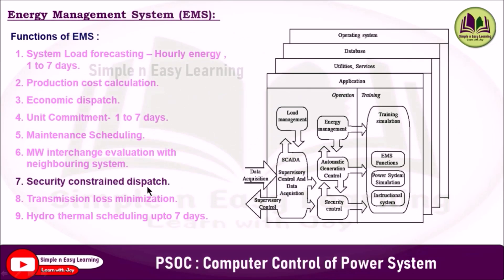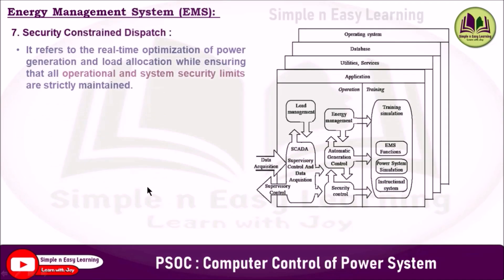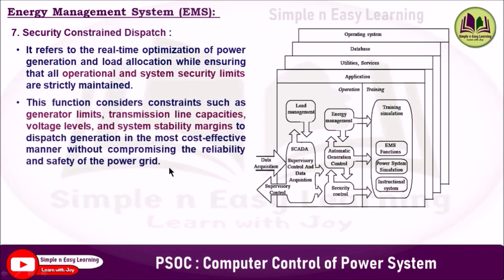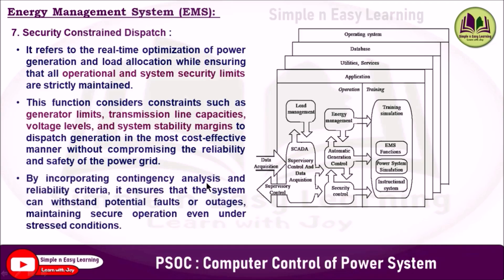The seventh function is security constrained dispatch. It refers to real-time optimization of power generation and load allocation while ensuring that all operational and system security limits are strictly maintained. This function considers constraints such as generator limits, transmission line capacities, voltage levels, and system stability margins to dispatch generation in the most cost-effective manner without compromising the reliability and safety of the power grid. By incorporating contingency analysis and reliability criteria, it ensures that the system can withstand potential faults or outages, maintaining secure operation even under stressed conditions.